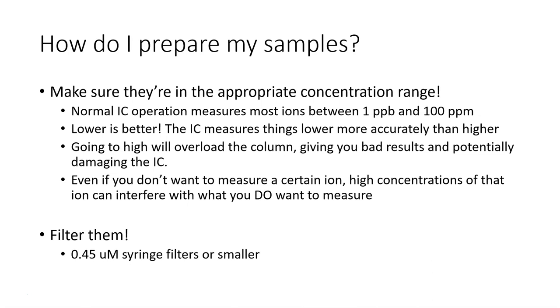The first thing you want to do is make sure that they are in the appropriate concentration range. Normally the IC measures most ions between one part per billion and a hundred parts per million. In general you want to go lower—lower is better. The IC measures things lower more accurately than it does higher. In addition to that, going too high is going to overload the column, give you bad results, and potentially damage the IC.